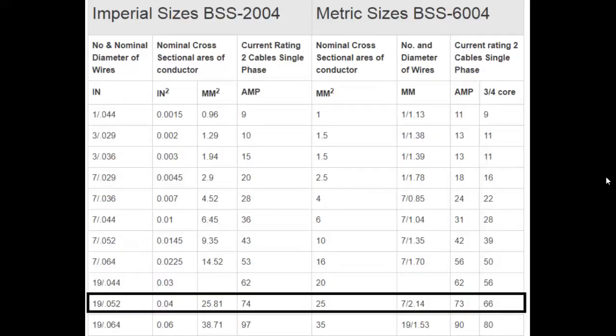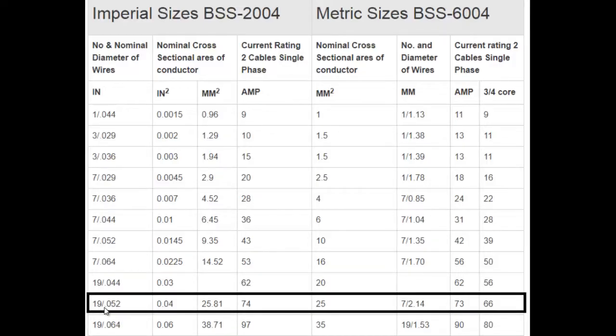Now you have two things: you have counted the total number of strands in a core, and you have also measured the diameter of a strand using a micrometer screw gauge. The next step is to refer to the table shown on the screen. On the first column, you can see the entry '19/0.052'. In my cable, there are 19 strands and each strand has a diameter of 0.052 inches. This corresponds to a nominal cross-sectional area of 25 mm² according to BSS standard 6004. So if you have these two entries, you can simply look into the table to find out the nominal cross-sectional area of a cable.